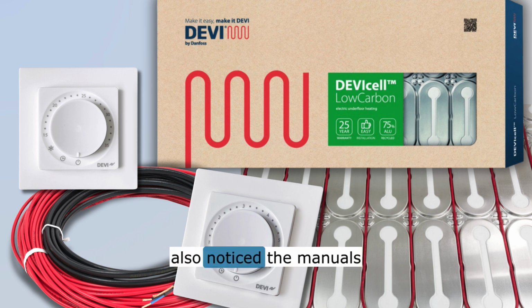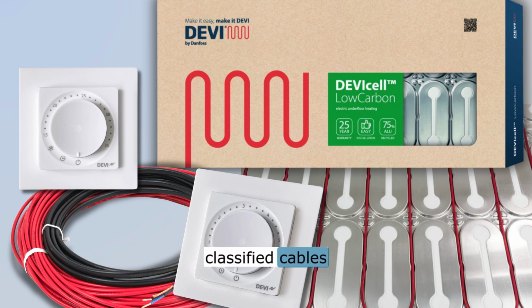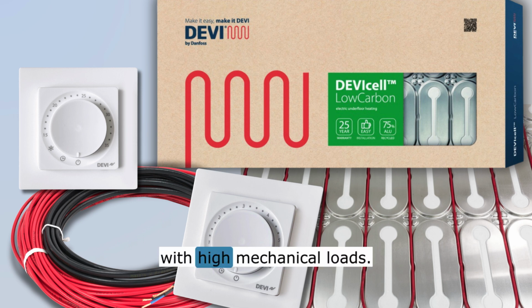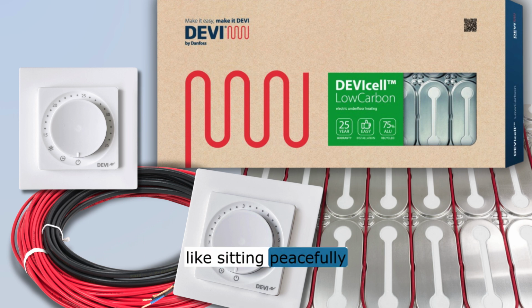Well put. I also noticed the manuals outline specific environmental classifications. They talk about M1 classified cables and explicitly warn never use M1 cables in areas with high mechanical loads. Right. So the M stands for mechanical strength. And M1 classification means the cable is designed for light duty, like sitting peacefully inside a bathroom floor. You would never put an M1 cable outdoors, in roof gutters, or tie it to steel reinforcing grids. It physically lacks the heavy-duty armor to survive being stepped on by construction boots or crushed by sharp stones in a heavy concrete pour.